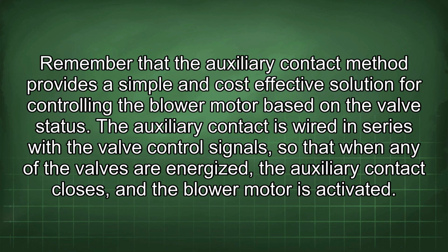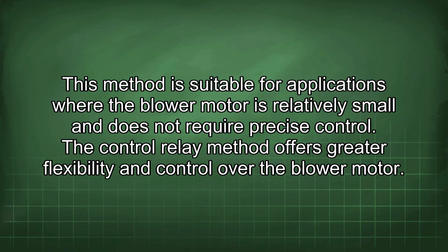Remember that the auxiliary contact method provides a simple and cost-effective solution for controlling the blower motor based on the valve status. The auxiliary contact is wired in series with the valve control signals so that when any of the valves are energized, the auxiliary contact closes and the blower motor is activated. This method is suitable for applications where the blower motor is relatively small and does not require precise control.